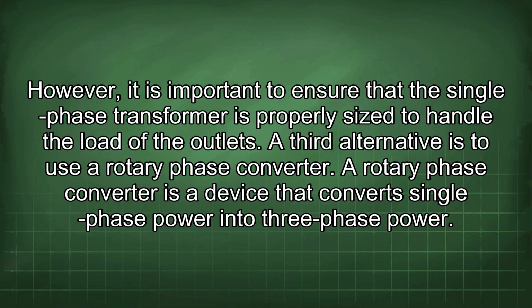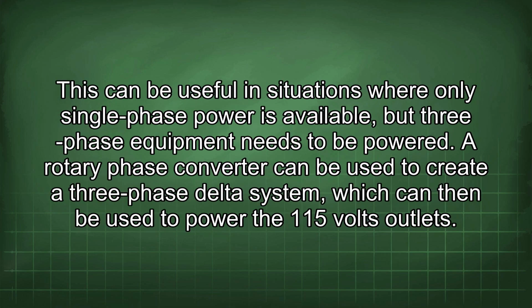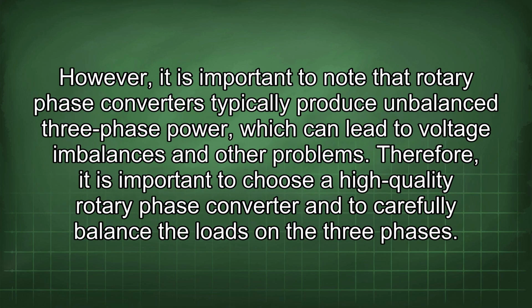A third alternative is to use a rotary phase converter. A rotary phase converter is a device that converts single-phase power into three-phase power. This can be useful in situations where only single-phase power is available, but three-phase equipment needs to be powered. A rotary phase converter can be used to create a three-phase delta system, which can then be used to power the 115 volts outlets. However, it is important to note that rotary phase converters typically produce unbalanced three-phase power, which can lead to voltage imbalances and other problems. Therefore, it is important to choose a high-quality rotary phase converter and to carefully balance the loads in the three phases.